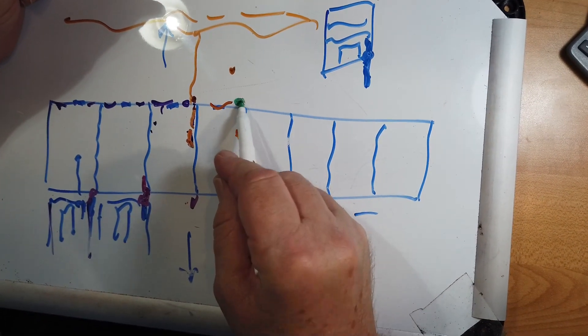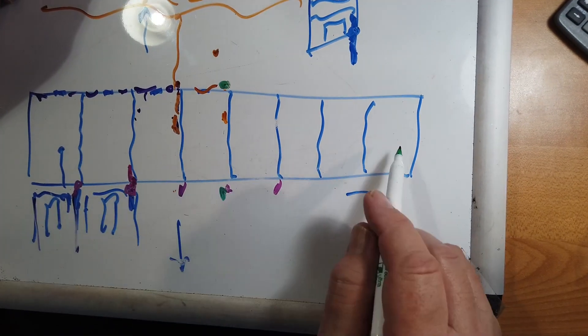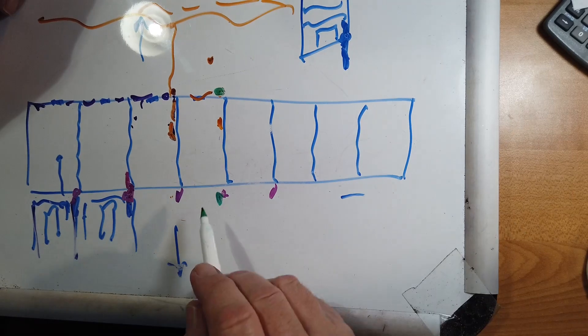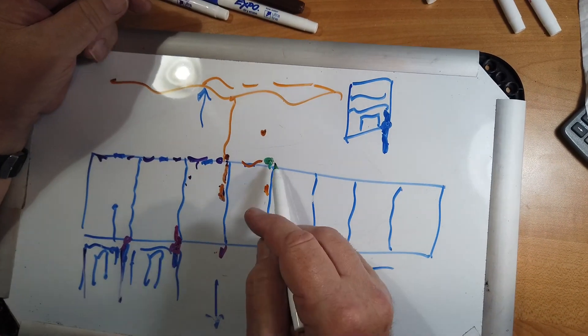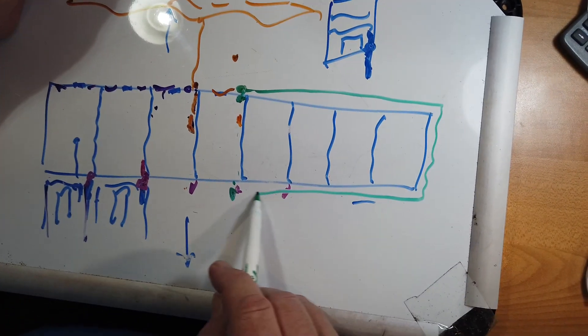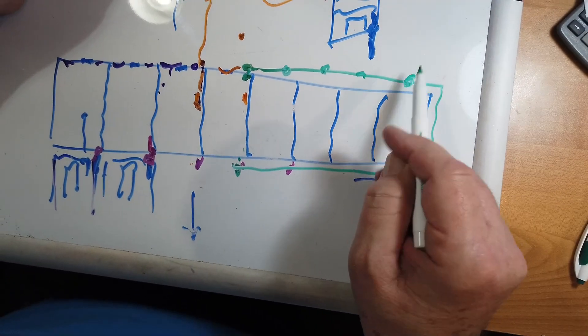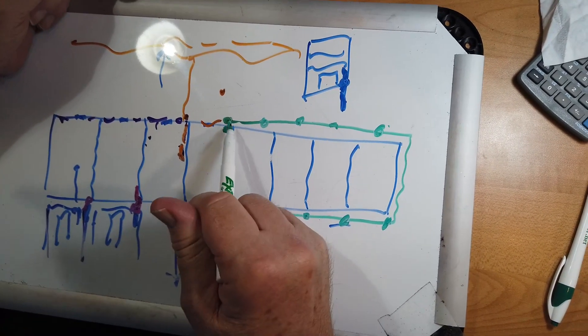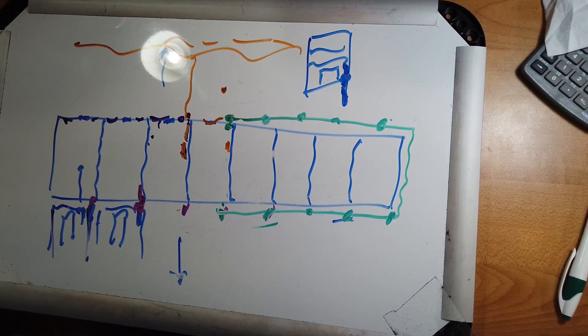So you've got this problem that your ground is out here, and the utility ground is utterly inaccessible. Now, if you go by the electrical code, this and this should be bonded together. But you never want the bond to run in the building. So what do you do? I mean, ideally, you would be able to tunnel underneath or in the concrete, below the concrete, below the rebar, or use an ufer ground that happens to be right there, or run a perimeter ground that's got ground rods around it that can support all of these. And there may be something to that effect over here. But what you've got to do is go to that one, and you really don't have a way of connecting to the other. Is that ideal? No, it's not ideal at all. Will it work? Yeah, probably.